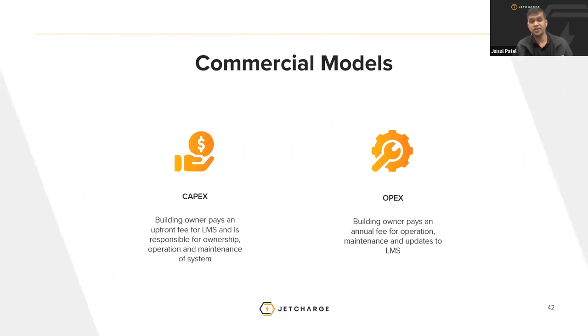In terms of commercial models, there's two different ways we can go about this. The first way is a capital expenditure model where the building owner pays an upfront fee for the load management system and is responsible for the ownership, operation, and maintenance of the load management system. The other option is the operating expenditure model where the building owner pays an annual fee, or can pass on that annual fee to tenants, for the operation, maintenance, and updates to the LMS. So the company that provides the load management system typically owns it for the lifetime of that system being installed in that building, but then the building owner does not have to worry about maintenance and updates to the load management system. Next slide.